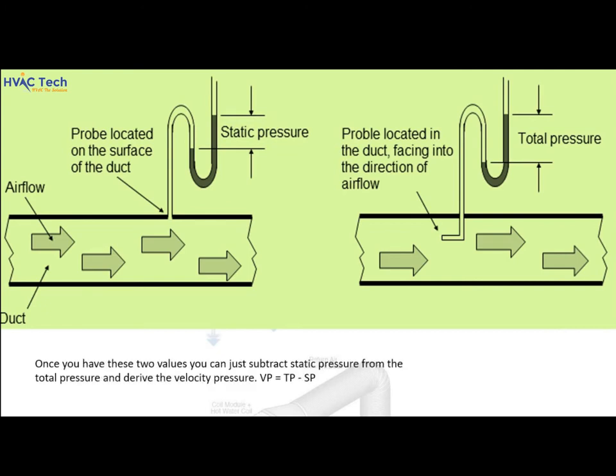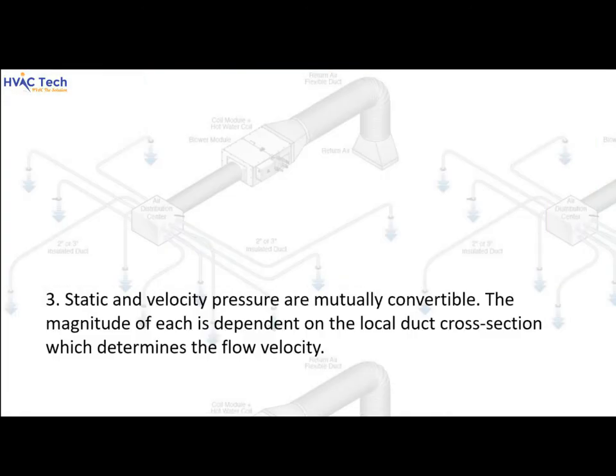Once you have these two values, you can subtract static pressure from the total pressure to derive the velocity pressure: VP equals TP minus SP. Static and velocity pressure are mutually convertible, and the magnitude of each is dependent on the local duct cross section, which determines the flow velocity.